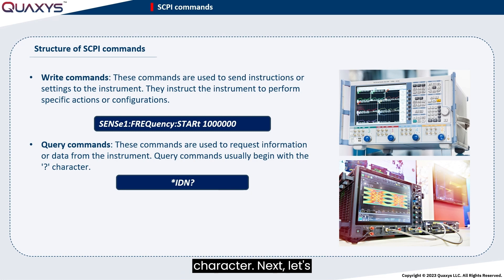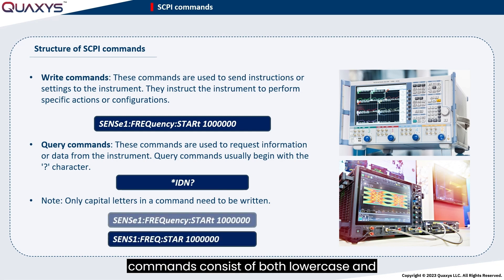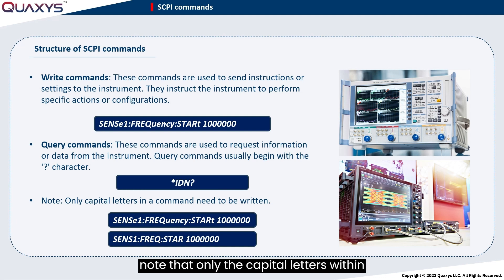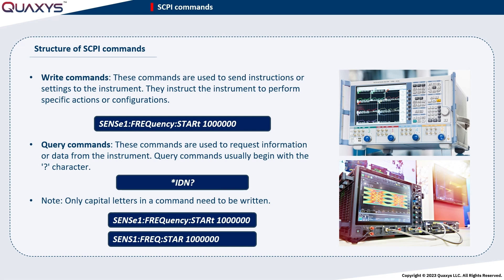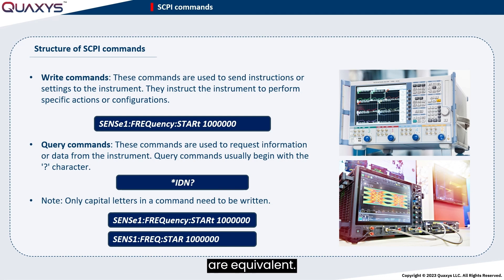Next, let's highlight a specific aspect of the SCPI command syntax. SCPI commands consist of both lowercase and uppercase letters. It's important to note that only the capital letters within a command need to be written. Therefore, these two commands shown here are equivalent.